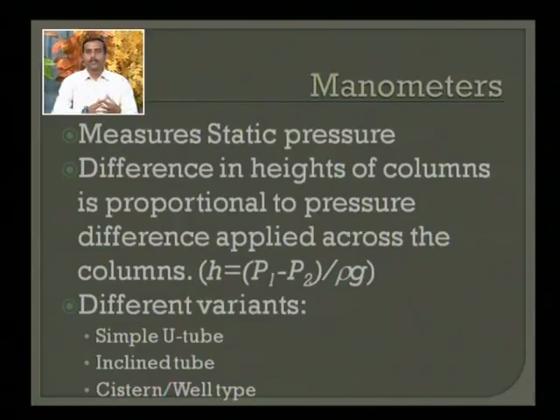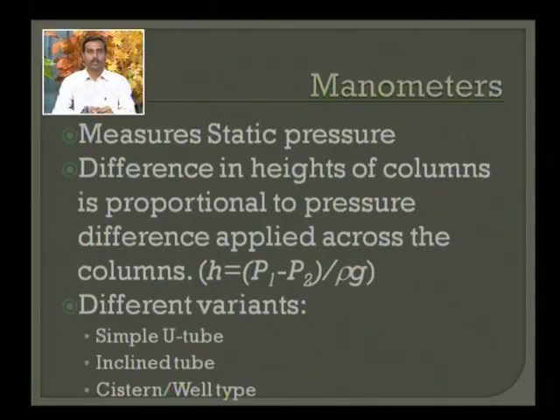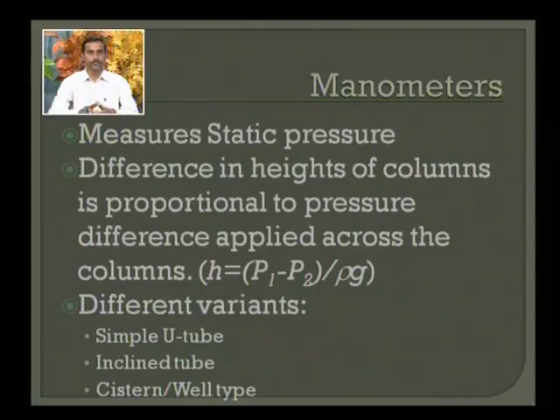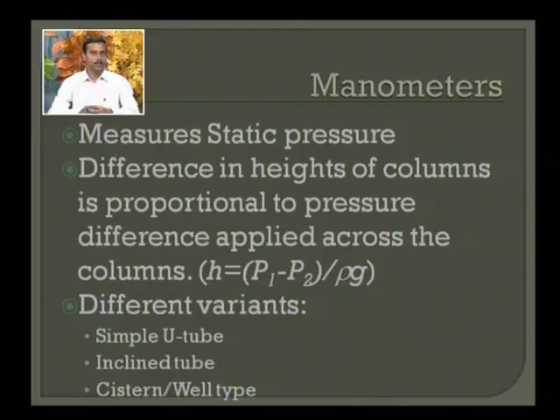Manometers measure static pressure; they cannot be utilized for dynamic pressure measurement. In a simple U-tube filled with liquid, if pressure is equal on both sides the level in both tubes will be the same. The difference in level indicates the difference of pressure on both heads. The expression is: h (height difference between the two menisci) equals pressure difference divided by rho times g, where rho is the density of the liquid. For lower pressure measurement use a light density material; for higher pressure use a higher density material.